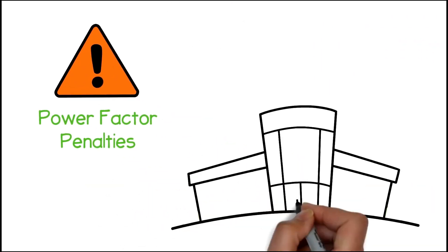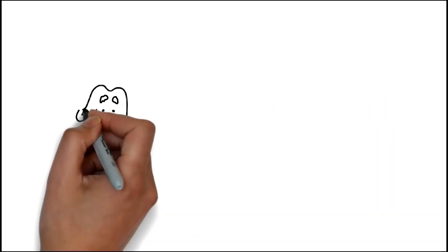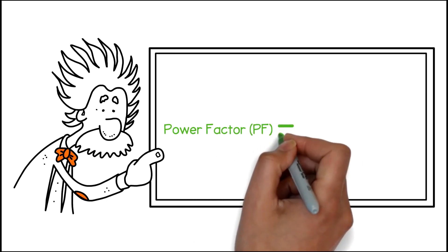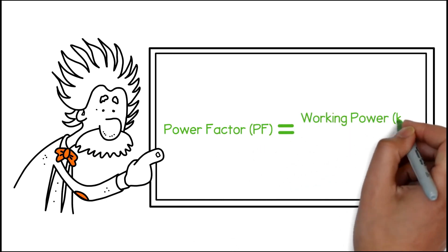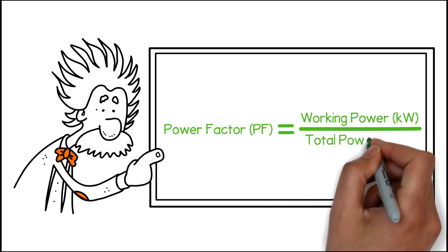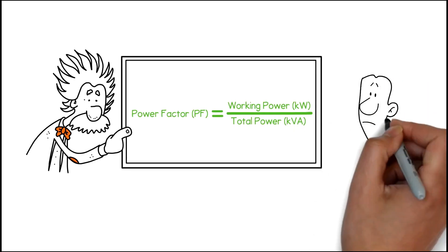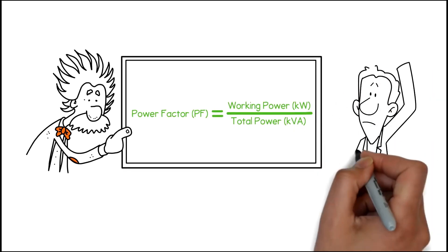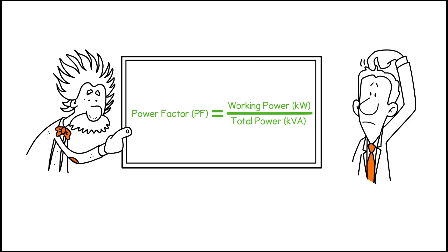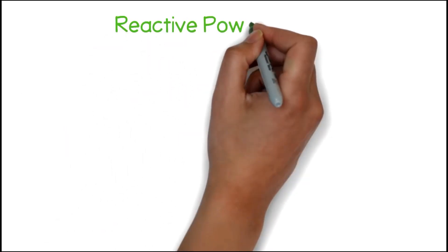Power Factor is a measurement of how effectively your premises uses its electricity. Power Factor is a ratio of the power used — called your working power or kilowatts — divided by the power supplied to you, called total power or KVA. The difference between working power and total power is called reactive power or KVAR.